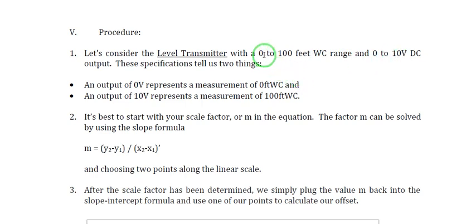So meaning for 0 feet of water level, your output is 0 volts. For 100 feet of water level, your output is 10 volts. So if you have a water level in the tank that's between 0 and 100, the output voltage should be between 0 and 10 also.